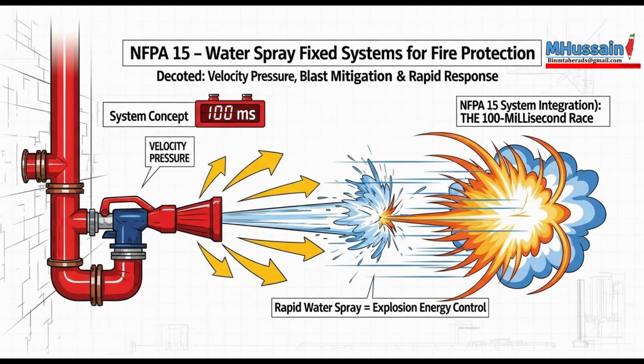So what are they explicitly not for? Section 12.1.2 mentions limitations. Crucial limitations. First, they are not for detonations where the combustion wave is faster than sound. Water sprays simply can't react fast enough. Second, they can't be used to suppress deflagrations inside enclosed or confined vessels if the goal is just limiting pressure buildup. For that specific scenario, engineers need to look at NFPA 69, which covers explosion prevention systems.